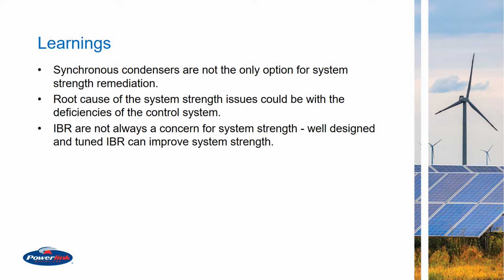In terms of the learnings that we have had from retuning of the control systems, synchronous condensers are not the only option for system strength remediation. The root cause of the system strength issues could be deficiencies in the control systems that are in place. So it is very important to understand the root cause of the system strength problem, as issues could be resolved by merely retuning the control system. And what I have shown you here is that IBRs are not always a problem in terms of system strength. If the control system is rightly tuned, IBRs can in fact supply system strength rather than consuming it.